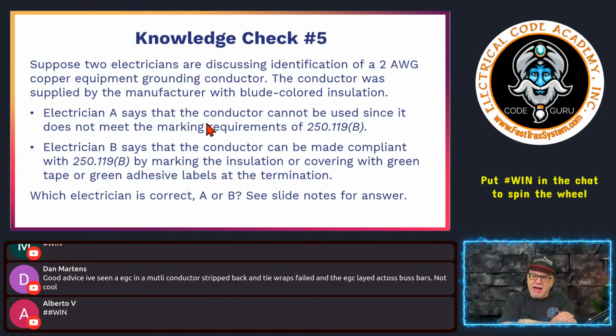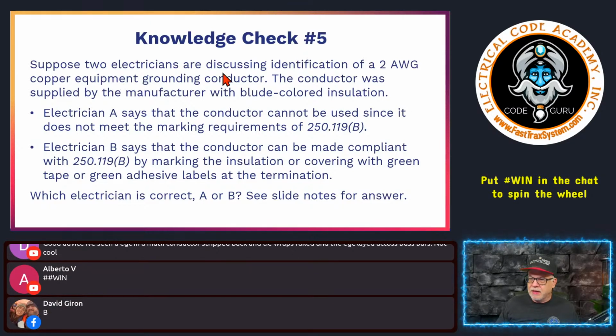Electrician A says that the conductor cannot be used since it does not meet the marking requirements of 250.119(B), right? And electrician B says that the conductor can be made compliant with 250.119(B) by marking the insulation or covering with green tape and green adhesive labels at the termination. Well, the first thing we need to figure out here is what it's dealing with. This is a water cooler argument between electricians.